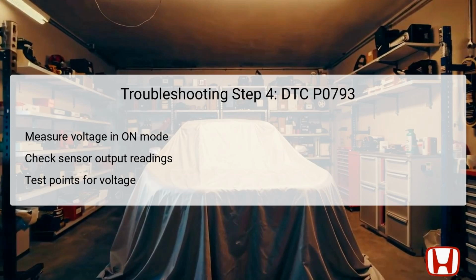If the voltage is confirmed as present, the sensor itself is deemed faulty, necessitating its replacement. Conversely, should the voltage not be present, this hints at an open circuit in the sensor ground 1, SG1 wire leading to the PCM, which also requires addressing.